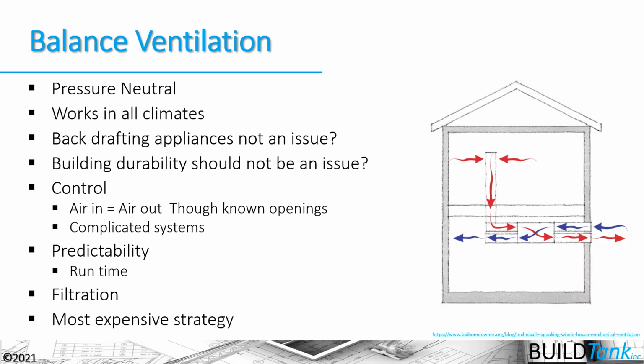We don't have backdrafting or combustion safety issues that we have to deal with. We shouldn't have building durability issues because we're not bringing uncontrolled air through the building envelope, either pushing it through or sucking it through, because we're taking it through actual ports designed for that ventilation strategy. I get my control and predictability again, because I know the quantity of air that's moving through the ventilation system, and I have a runtime again. What's also nice is that I can filter that air, but the downside here is that it's the most expensive strategy.